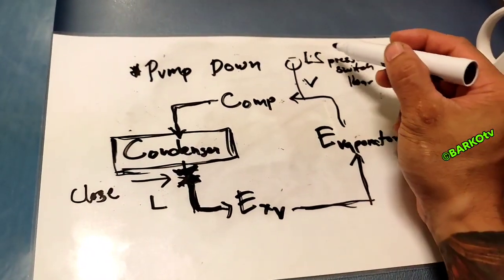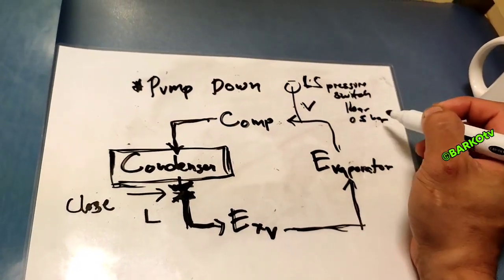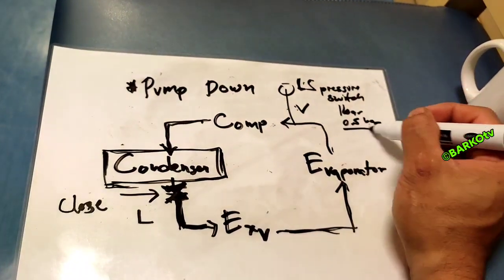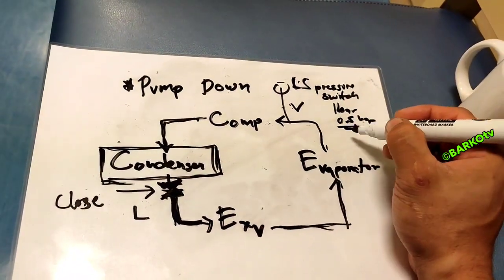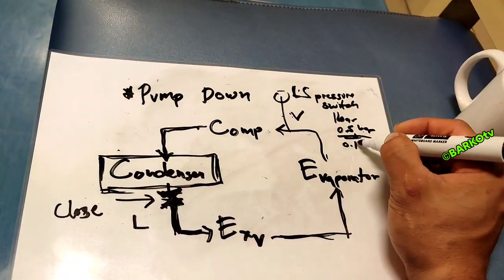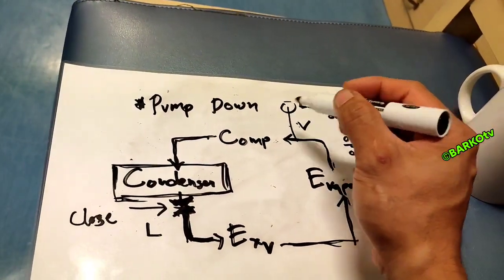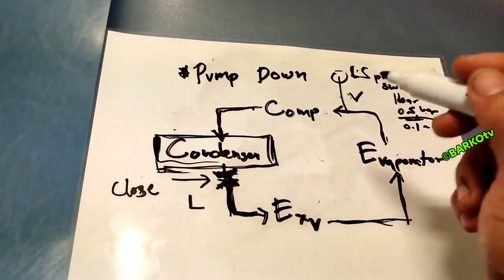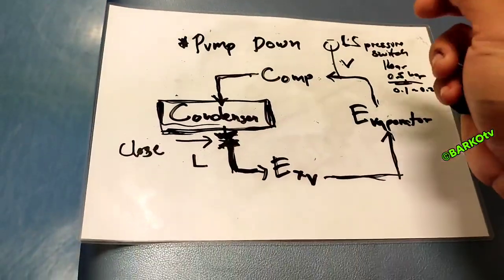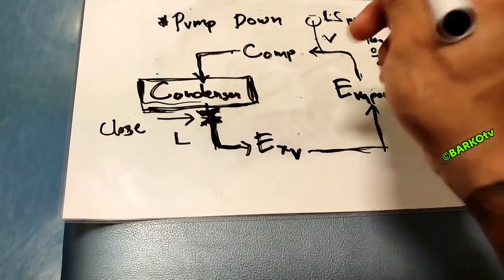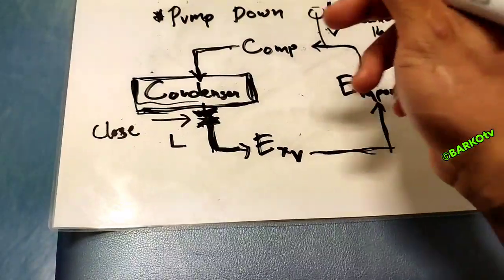For example, if the setting of the low pressure switch is 1 bar, once the system reaches 1 bar the compressor will auto shut off. If the setting is 0.5 bar, the compressor shuts off at 0.5. But if you want to do more pumping down, just override the low pressure switch down to 0.1 bar to collect almost the total amount of refrigerant going to the condenser.